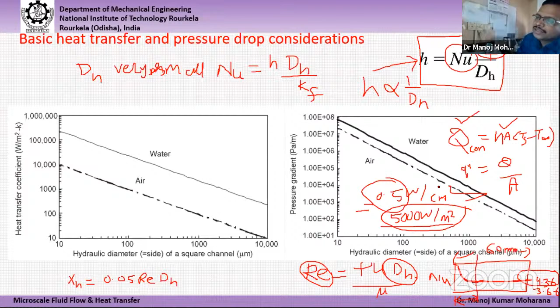However, considering that surface area per unit volume is more, the pressure drop will also be very high. You can see in this plot that by decreasing the hydraulic diameter in this direction, the heat transfer coefficient is increasing for water and air, and along with it the pressure drop is also increasing. So using mini or micro channels, heat transfer increases, but the pressure drop also increases.